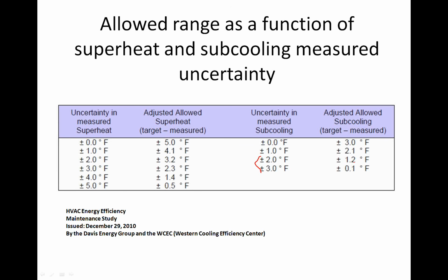So if it calls for 10 degrees of subcooling, we need to charge the system to exactly 10 degrees of subcooling to be within plus or minus 3 degrees. We've got to be within that 1 degree. So you have to take the time to actually set the equipment up properly to nail that target as close as possible. Otherwise, you're not going to be within the manufacturer specified subcooling. This becomes very important to do correctly because it directly impacts the performance of the equipment. When we look at an analog gauge, it's absolutely impossible. So if you're installing these high efficiency systems with analog gauges, you're probably not getting your charge correct.